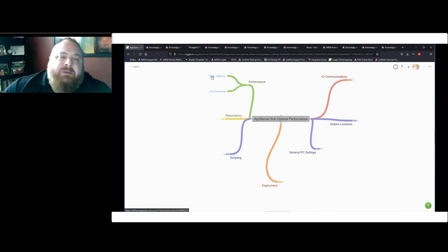You typically see scan overruns when you have deployments, or if you have a lot of on-scan startup scripts and things like that. What I tell people is if your scan overruns are less than 5%, that's okay. It's not ideal, but it's not a horrible thing. There's going to be drift in the system. There's going to be things that happen, like when this process spikes up and eats the CPU that we need. So if it's less than 5%, I wouldn't worry too much about it, unless you're having other problems, since this can be an indicator of other problems.